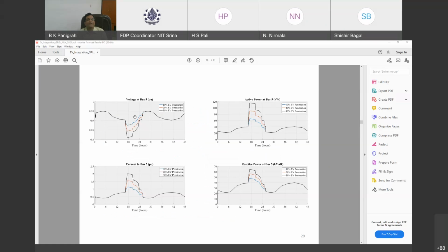Now, why is this fluctuation there? The fluctuation you can see here is because the charging takes place from this point and the charging finishes here. So if we penetrate 10%, 20% and 30%, now you can see there is a significant voltage drop. The voltage may drop as low as 0.81 per unit. Why is there a voltage drop?